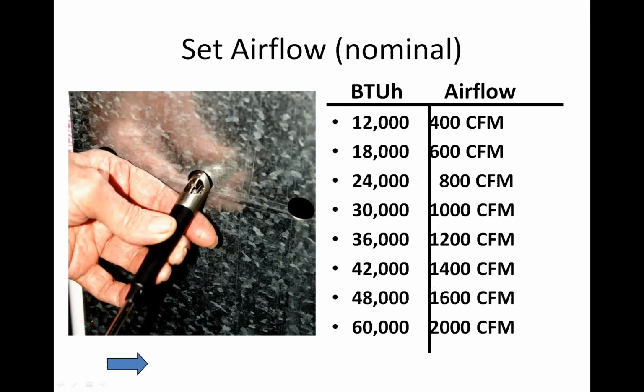When we talk about setting airflows, we're talking about nominal airflows. So typically we're talking 400 CFM per ton, and this is just a chart of 12,000 BTUs, 400 CFM, 18,000, 600, all the way down the line. If we were going over 5 tons, obviously this ratio stays the same. Some manufacturers do have systems that operate at less than 400 CFM a ton. Carrier makes a system that operates as low as 350 CFM per ton.